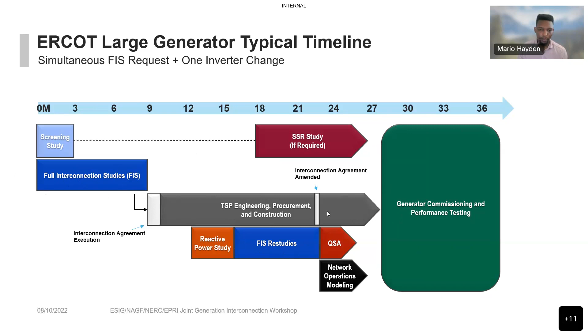The first study performed in the interconnection process is the screening study. This is a high-level FCITC that, based on the point of interconnection selected by the generator and the commercial operations date, gives an idea of the steady state injection capacity at that point of interconnection. No generator-specific models are required at this stage—really what you're providing is size, fuel type, location, and desired connection date. The most important output is that ERCOT will perform at minimum a topology screening of the POI to determine if an SSR study is required, which could lengthen the process or put the project's ability to synchronize at risk.